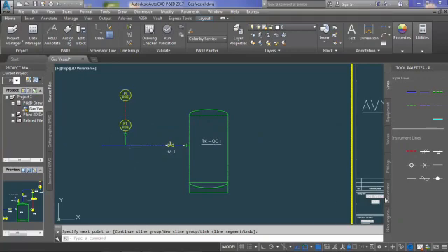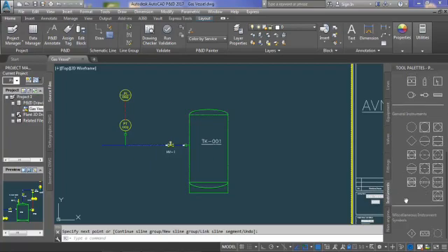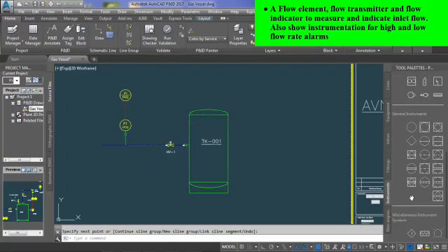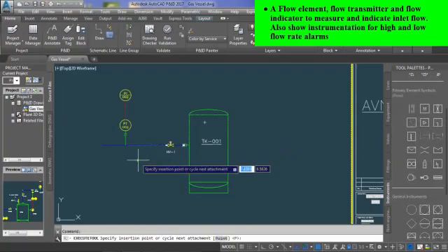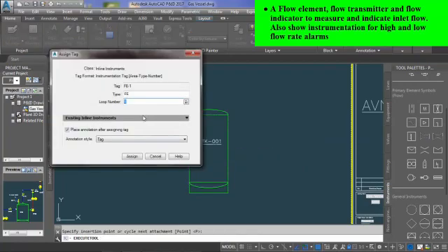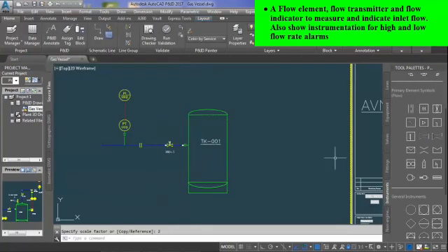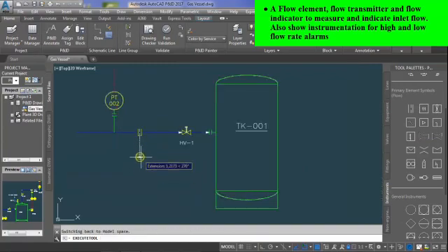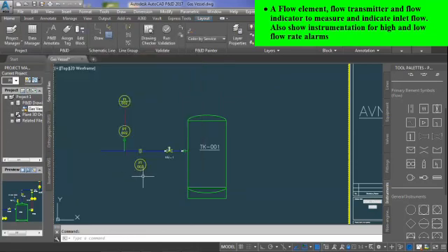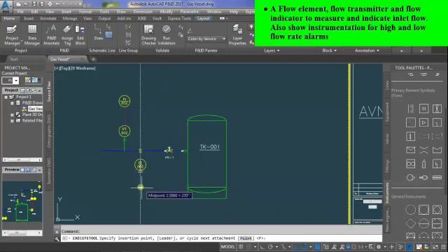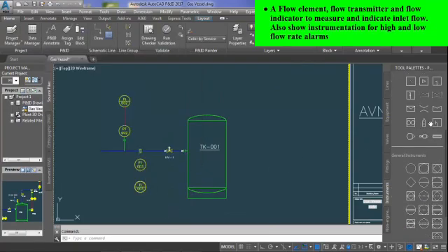After adding pressure monitoring instruments, the next requirement is to add instruments to monitor the flow of gas with high and low flow rate alarm. First from instruments, add orifice which is a flow element and tag it FE-3. Then add field discrete instrument for flow transmitter and tag it FT-3. Next instrument to insert is flow indicator and tag it FI-3.